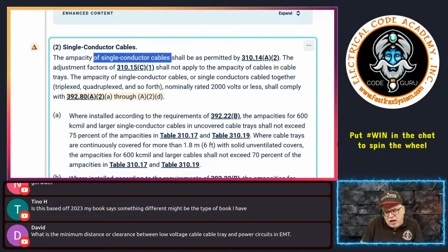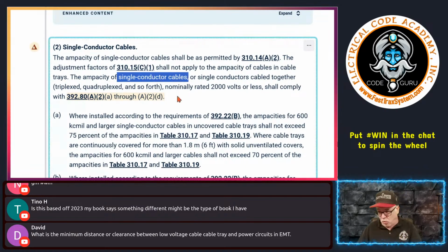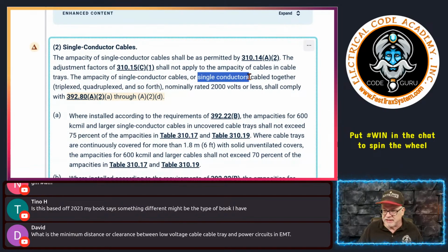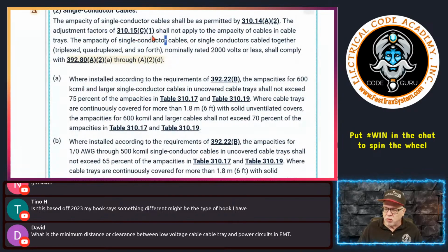Well, how do you determine an ampacity if you're allowed to install them in an industrial establishment, and we're allowed to put them in a tray, and they have to have an ampacity? If this didn't apply, then what's the ampacity of the conductors in that tray? So you're just going to have to realize that that's what it's talking about: single conductor cables, or here it says single conductors, that type of thing. Anyway, so we don't have to apply 310.15(C)(1) to that application.